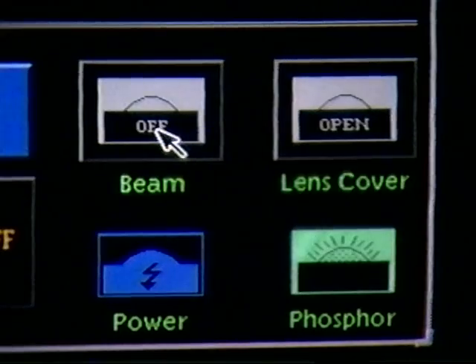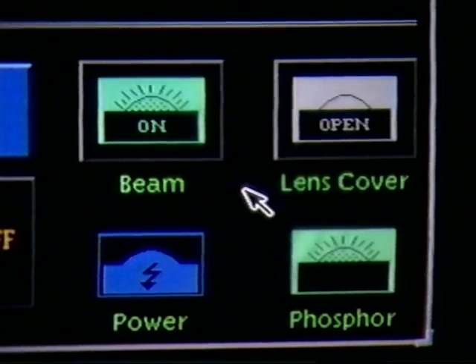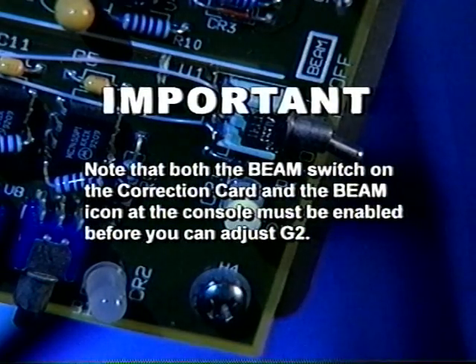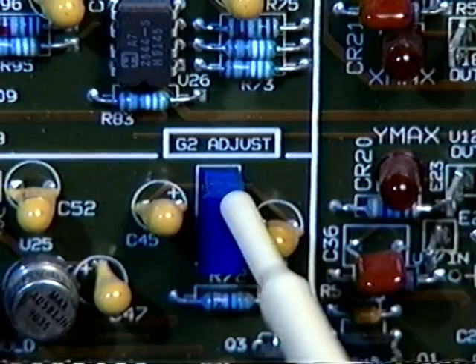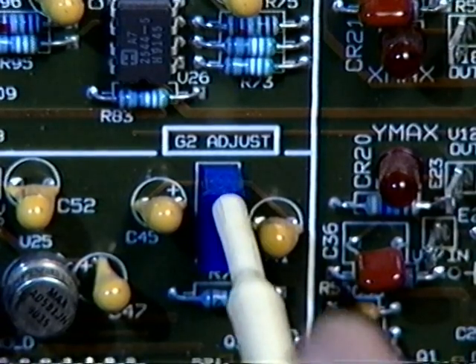Click the beam icon at the console so that it turns green. Important: note that both the beam switch on the correction card and the beam icon at the console must be enabled before you can adjust G2. Slowly turn G2 clockwise until a faint glow is seen in the projector's lens. As soon as you notice individual patches of light, stop turning the G2 control.